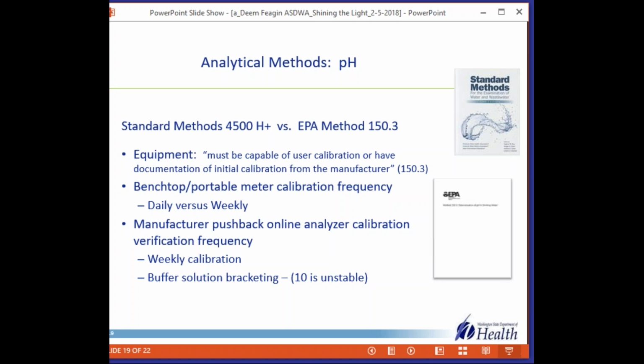So quite frankly, we were just going to delay this one until people on the line popped in with the right answers, but all of you are quite silent here on question number 8. Well, one thing that is interesting is that the less expensive pH meters, which include all the ones that we own, recognize 4, 7, and 10 for calibration. They don't recognize 8.2 or any other buffer. So your choices are 4, 7, and 10 for our field instruments. I know the more expensive ones, you can tell it whatever you want to tell it.